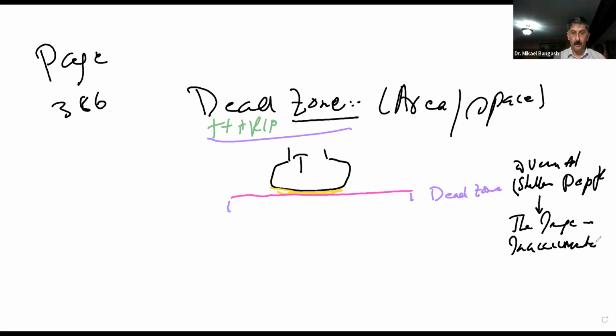Which mainly would mean that if, for instance, we intend to scan a structure which is in the dead zone, that's why a standoff pad is used to do so. It just makes a fake dead zone.